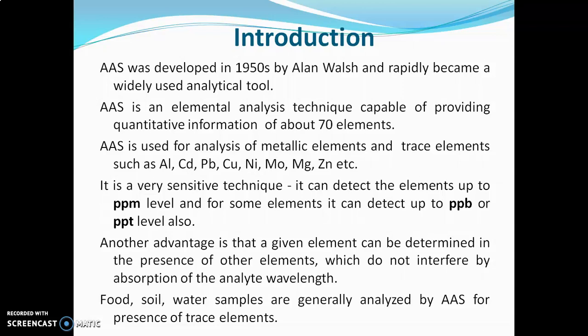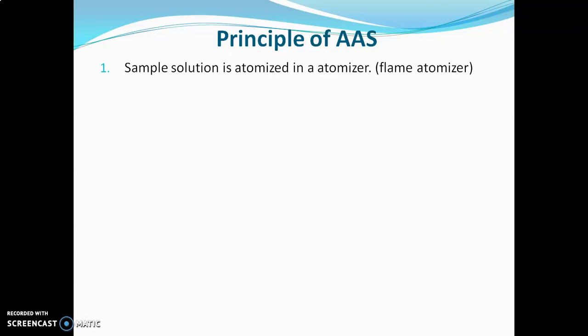In AAS, food, soil, and water samples are generally analyzed for the presence of trace elements. Now we'll go to the principle. The principle of AAS and flame photometry is almost the same but differs at a particular point. The first step involved is that the sample solution is atomized in an atomizer. An atomizer is a part of the AAS instrument which converts a solid or liquid sample into gaseous metal atoms. Many types of atomizers are available, but the most commonly used is the flame atomizer.